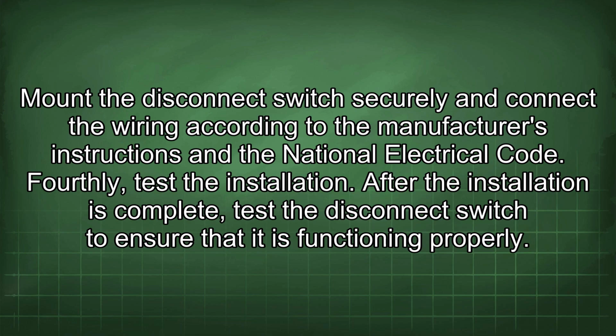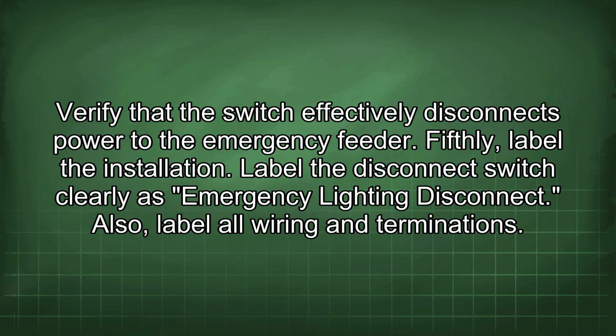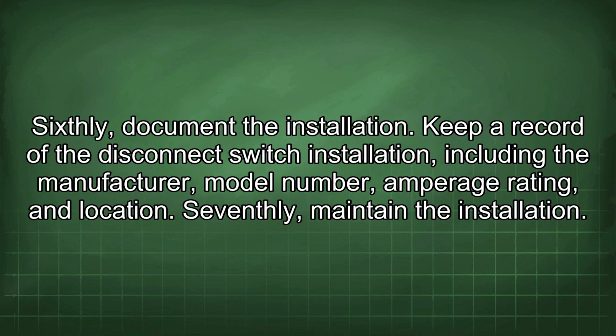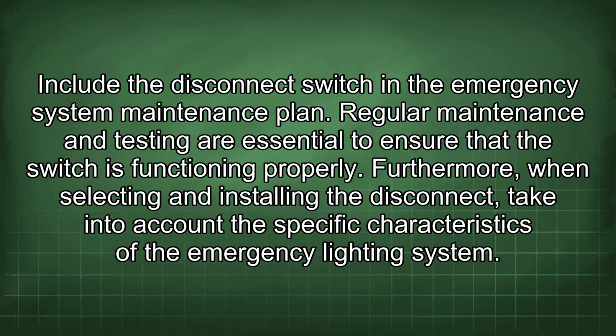Fourthly, test the installation. After the installation is complete, test the disconnect switch to ensure that it is functioning properly. Verify that the switch effectively disconnects power to the emergency feeder. Fifthly, label the installation. Label the disconnect switch clearly as emergency lighting disconnect. Also, label all wiring and terminations. Sixthly, document the installation. Keep a record of the disconnect switch installation, including the manufacturer, model number, amperage rating, and location. Seventhly, maintain the installation. Include the disconnect switch in the emergency system maintenance plan. Regular maintenance and testing are essential to ensure that the switch is functioning properly.